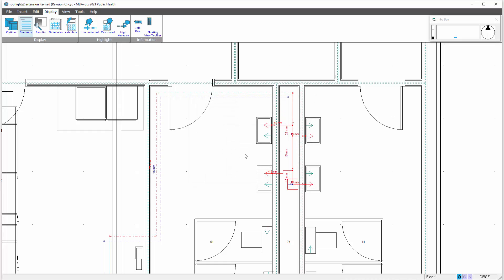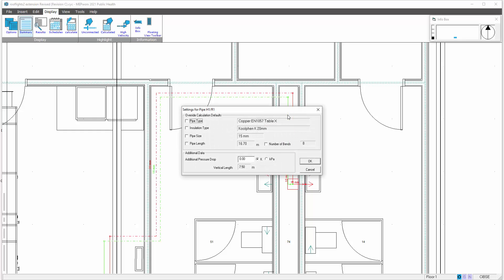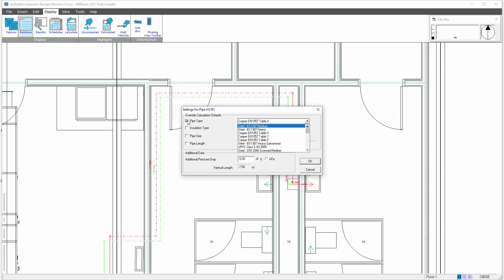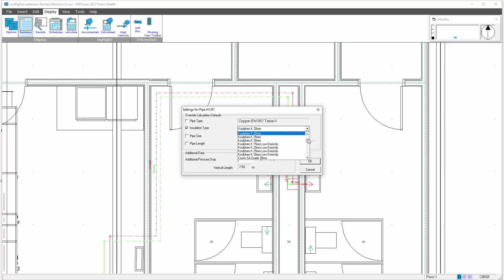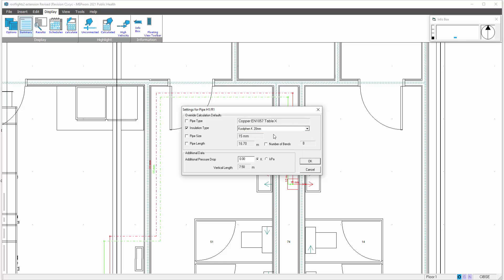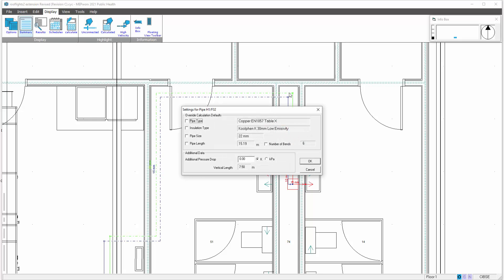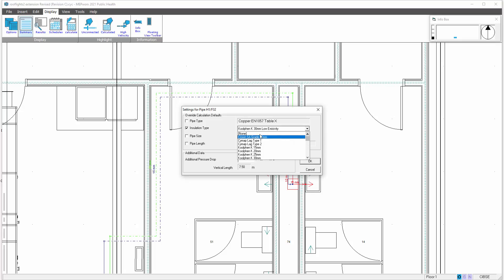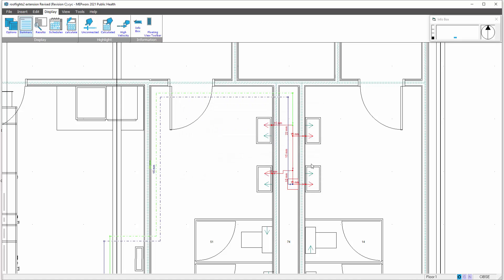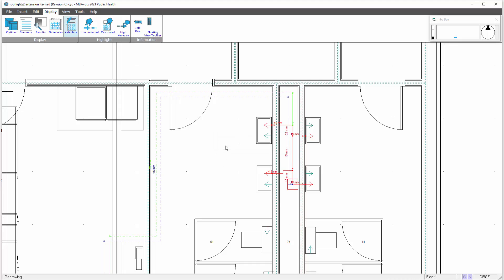What we can do to demonstrate the flow rates is go into the various pipes and strip off the insulation. If I increase the emission from the pipe work by stripping off all the insulation those flow rates will change. Pipe type insulation type can be changed, and that will induce flow rate based on the pipe emissions. Do the same on this run with the insulation type, display calculate water.